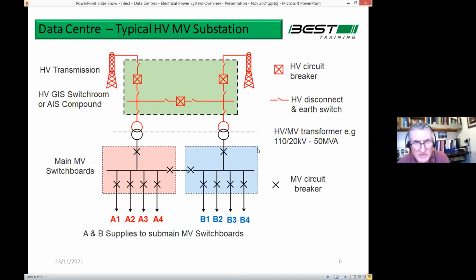And we're going to explain a little bit about resilience and redundancy. Everything is duplicated in data centers. If the A system fails, you have a B system to back up. It's typically done like this. You have an input circuit breaker, then a number of feeders going out to your other transformers around the site, and the two boards are coupled together here. So if you want to take one of the transformers out of service, you can join the two boards together, etc. Lots of different configurations.